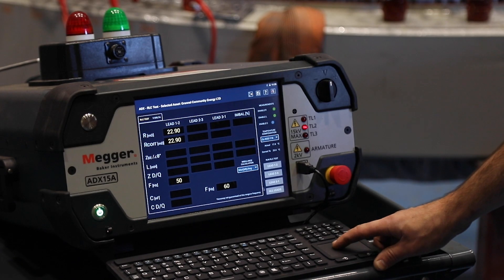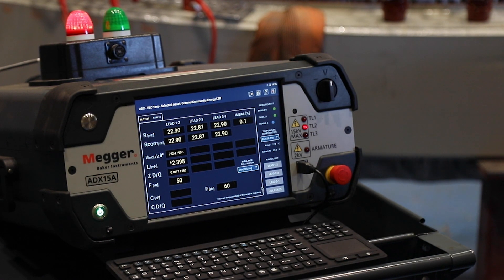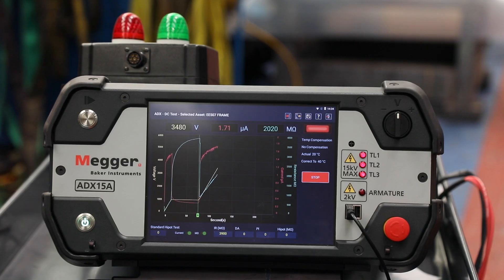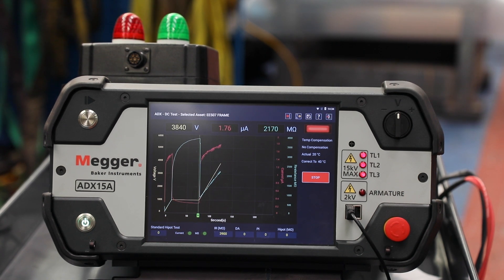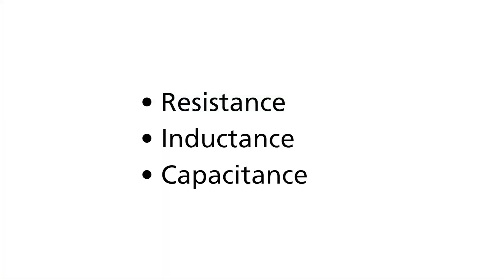Ground wall testing is done with a megohm test, but the megohm test alone is an incomplete test of ground wall insulation. To completely test the ground wall insulation, high voltage step, ramp, and high pot tests are also used. Baker Instruments static motor tests are non-destructive and follow IEEE and IEC motor testing standards. Additional tests available include resistance, inductance, and capacitance for verification of motor winding construction.